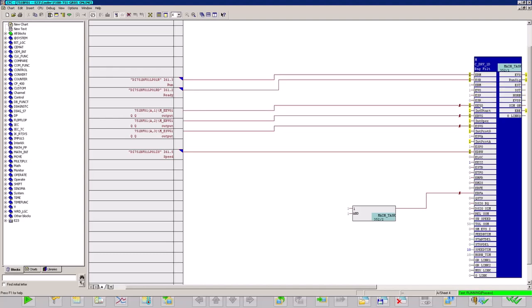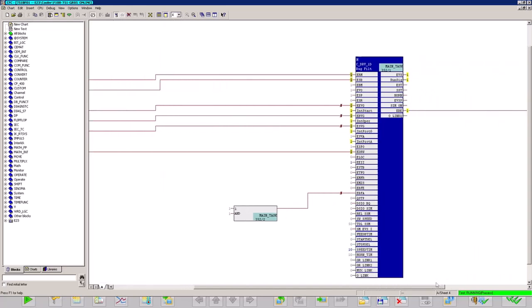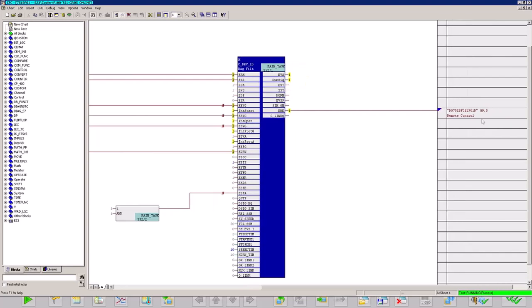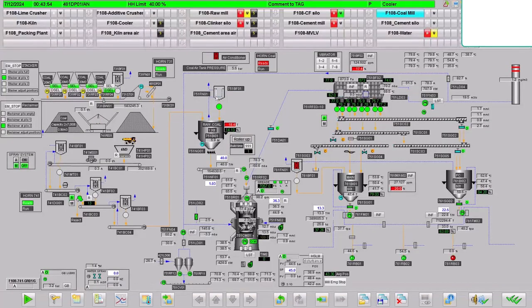This is how I will observe the various signals. As you can see, the readiness signal, the feedback signal, the start interlock, operation interlock, protection interlock, speed monitor, and the command. This device is currently in operation and all the bits are high.